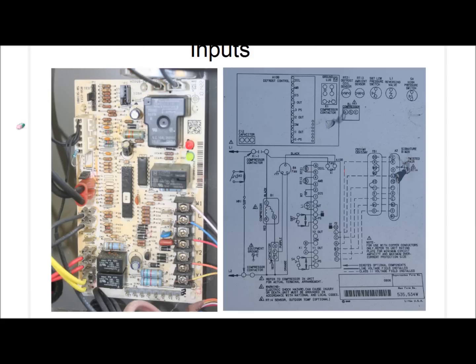All right, so we'll do a quick review. Y terminal, 24 volt signal to turn on or off the condensing unit. O terminal, 24 volt signal to energize or de-energize the reversing valve. R, constant 24 volts for the control board power. C, the 24 volt return voltage. And one of these terminals up here, the top left one, is one leg of the 230 volts for the condenser fan.